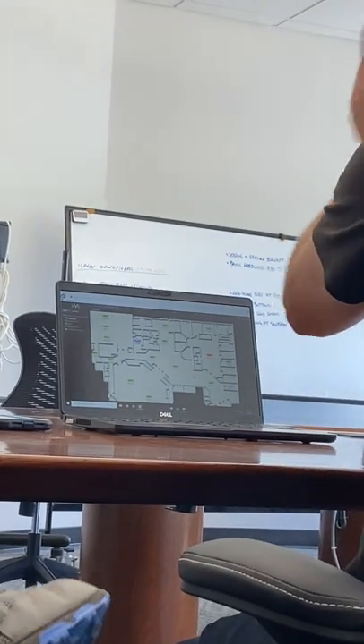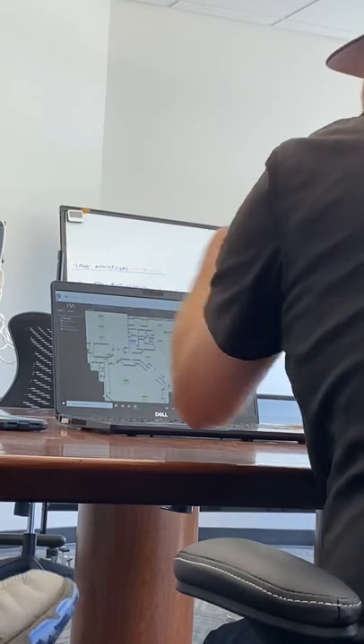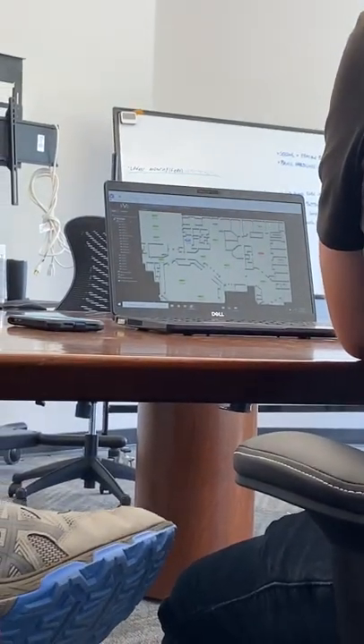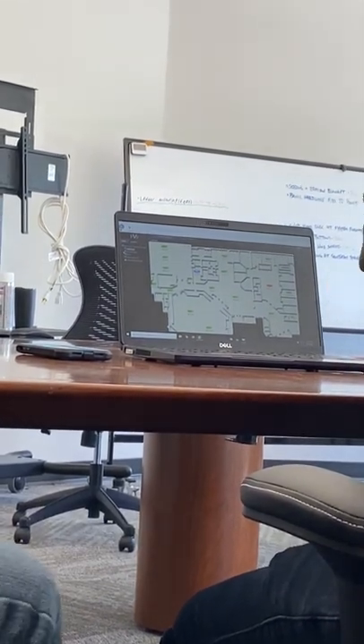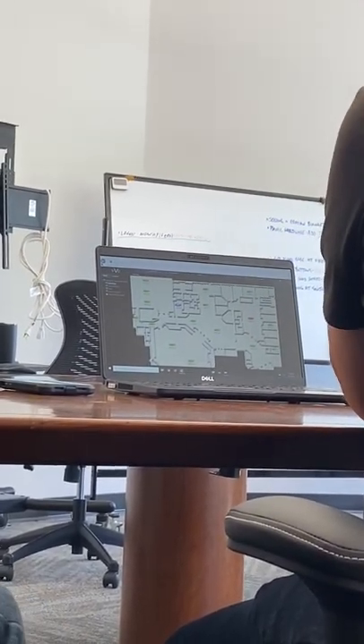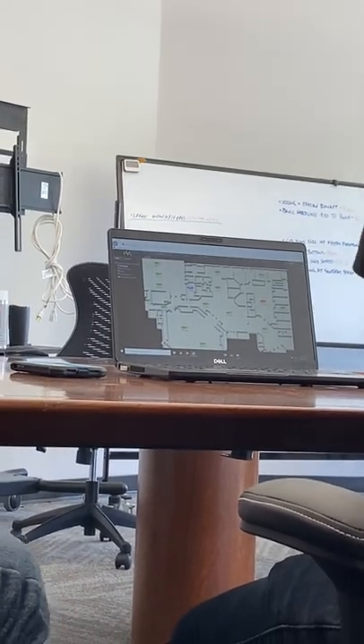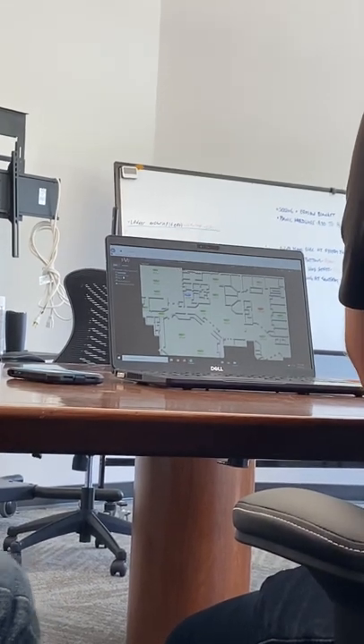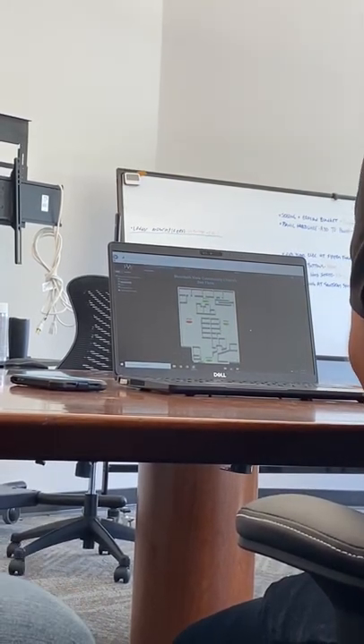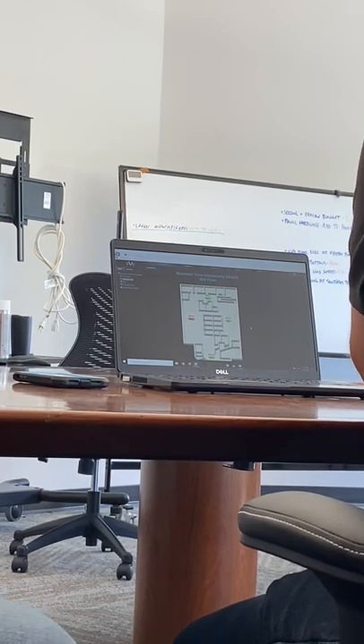So the four rooftops on this side of the building — you'll notice on the first floor there's a drop-down arrow, and that's where all the devices are for first floor. On the second floor there is also a drop-down arrow because all of those four rooftops over here feed both levels. So R2-8 feeds up here and then down on the first floor on the same side. And those are on the Zonex system. So some of those existing units are on a completely different system that are integrated into this.